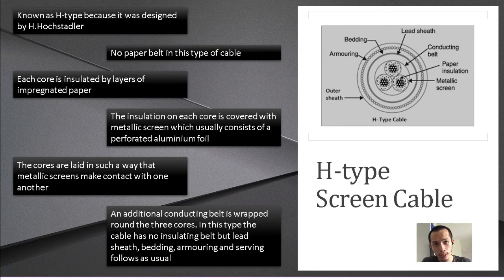So the first one, known as H-type because it was designed by H. Hochstadler, with no paper belt in this type of cable. Each core is insulated by layers of impregnated paper, where the insulation of each core is covered with metallic screen, which usually consists of perforated aluminum foil. The cores are laid in such a way that the metallic screens make contact with one another, as you can see in the provided diagram of the H-type cable.